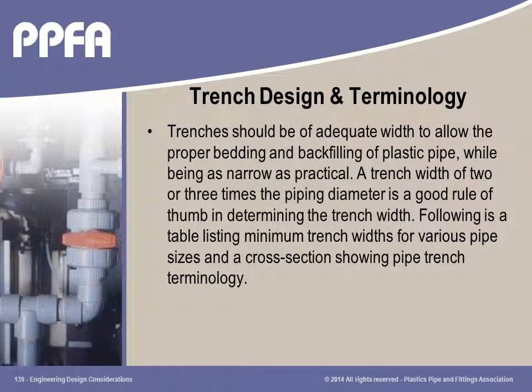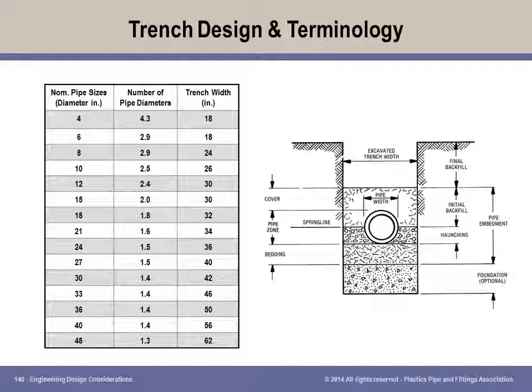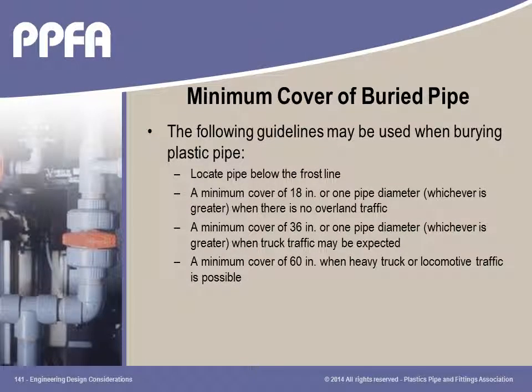Trenches for thermoplastic piping should be as narrow as possible to improve the pipe integrity with the compacted soil. See the listed table and check with the pipe manufacturer for additional information. Pipe burial depth is a critical design consideration based on ground traffic and geographic location with thermoplastics as well as other non-plastic piping systems.